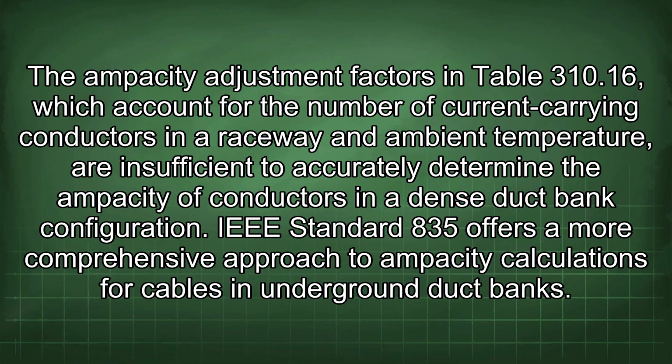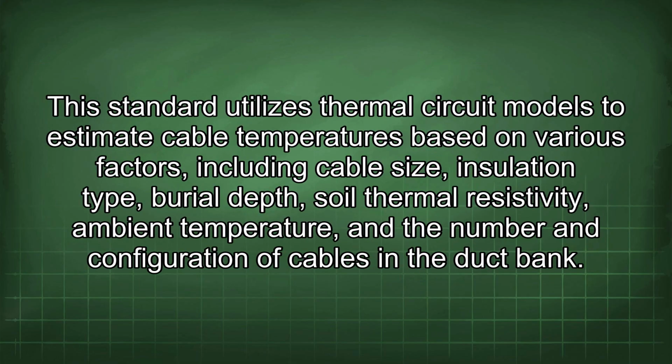IEEE Standard 835 offers a more comprehensive approach to ampacity calculations for cables in underground duct banks. This standard utilizes thermal circuit models to estimate cable temperatures based on various factors, including cable size, insulation type, burial depth, soil thermal resistivity, ambient temperature, and the number and configuration of cables in the duct bank.